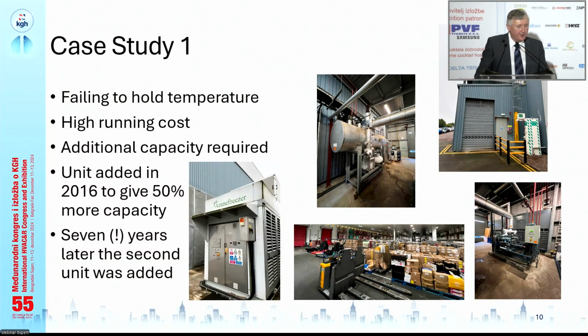The running costs were very high. The customer felt that he needed a bit more cooling capacity to keep the room down to temperature. So we supplied a package unit, a standalone ammonia package unit, to give 50% more capacity to the chamber. And what we learned was that 50% additional capacity was enough to keep the store temperature down most of the time. Occasionally, the old plant had to kick in and run as well, but for 90% of the year, we ran only on the smaller plant. That doesn't make sense. That really doesn't compute. If the big plant wasn't holding the temperature, the small plant should definitely not be holding the temperature.